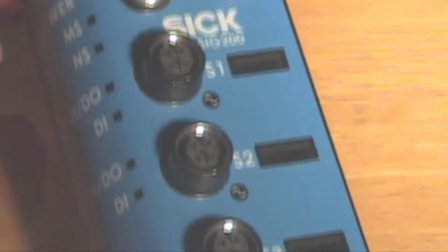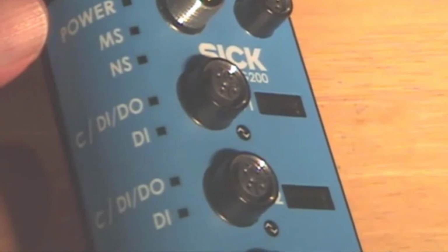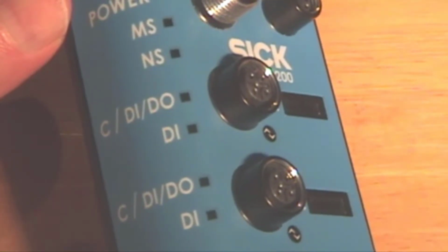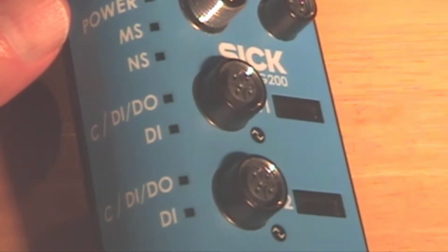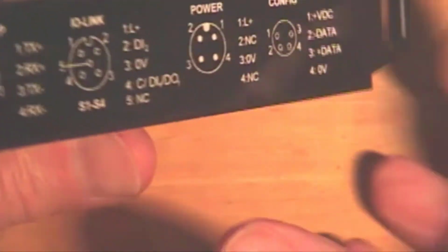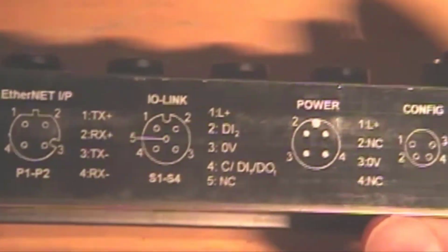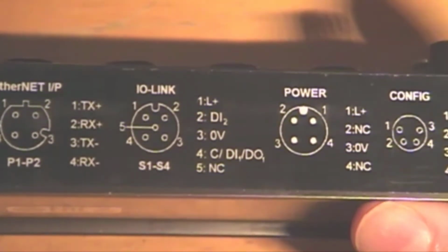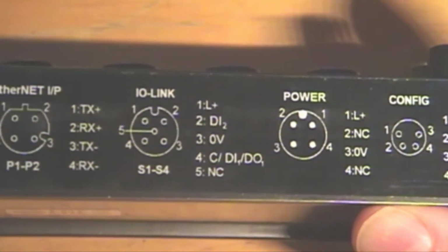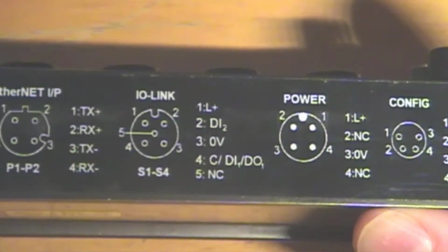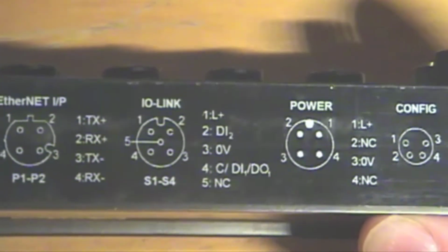Here you can see there are a number of ports, S1 through S4 for connecting devices, and then a couple of different ports. Two ports for the Ethernet TCP/IP or Ethernet IP connection. Each one of the ports has a digital output and a digital input, pins 2 and 4, and that is further detailed on the side of the device, looking at the IO link port, where the digital input is on pin 2 and the configurable input output is on pin 4.